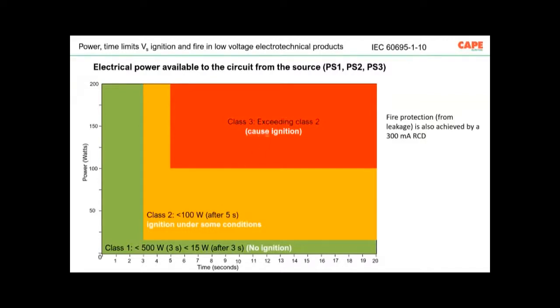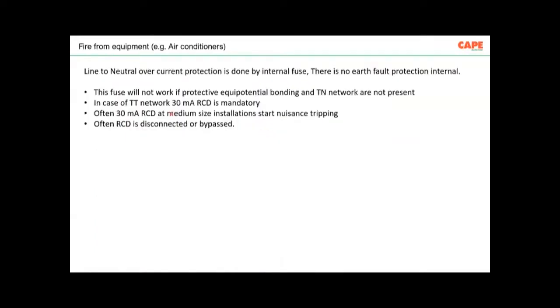So power supply classification is very much necessary, especially for equipment. Let us say for an air conditioner. You have an air conditioner, and it has an internal fuse. Whenever there is a fault, whenever there is a short circuit or an overcurrent between line and neutral, then your fuse will blow and the device is disconnected from the circuit. But the same fuse will not disconnect whenever there is an earth fault. If you want your air conditioner to disconnect, then your earth fault loop impedance must be negligible. Then only it will work out. Otherwise, you have to have a 30 milliampere RCD at every installation.